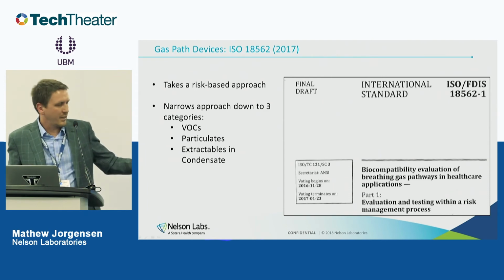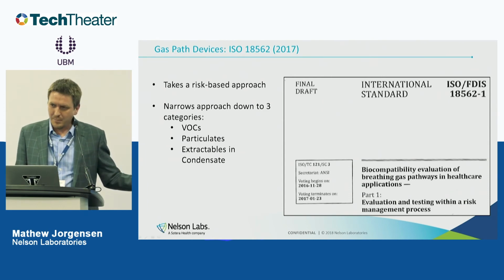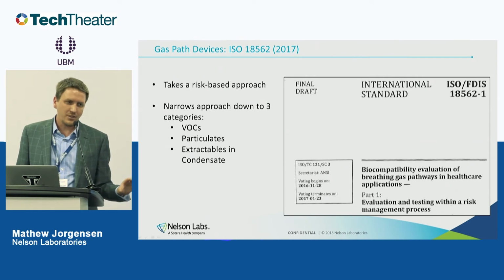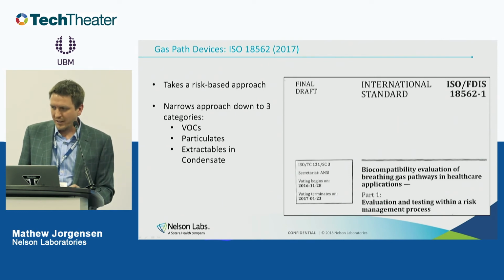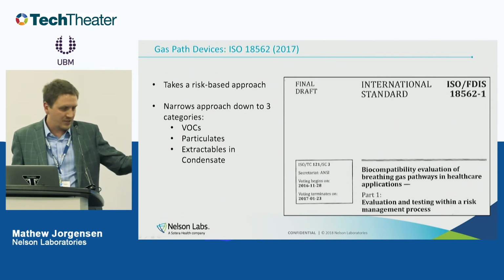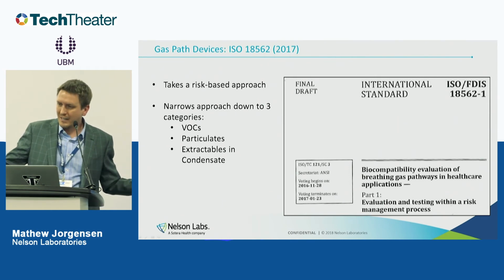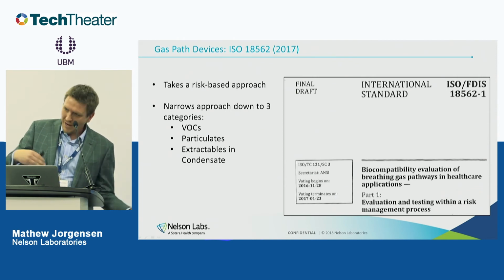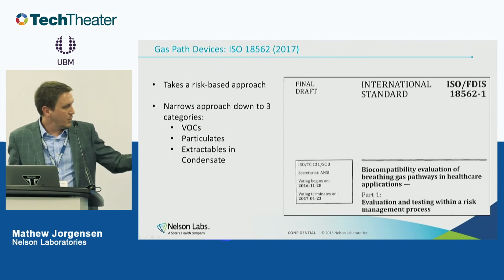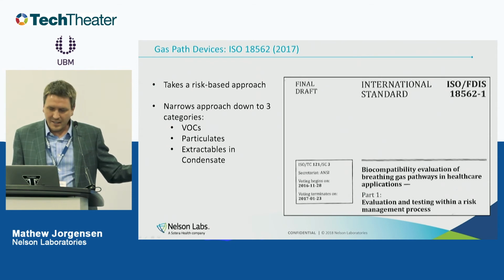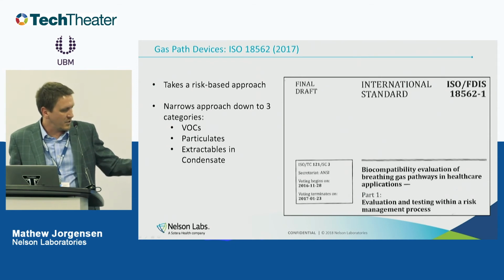So this is really common sense for gas path devices. If you have a gas path device, you really must test to 18562. Now, the regulators aren't accepting anything outside of 18562. If you do 10993, they'll say, great, now go back and do 18562. So it's really common sense. I love it from a scientific perspective.